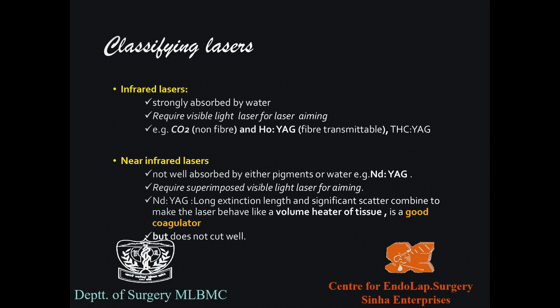Infrared lasers are strongly absorbed by water. Because they are in the infrared range they are invisible, so they require a visible light for aiming — a visible beam is combined so you know where the laser is going. The most common example is the carbon dioxide laser, which cannot be delivered through a fiber, and the holmium:YAG laser, which can be delivered through a fiber.